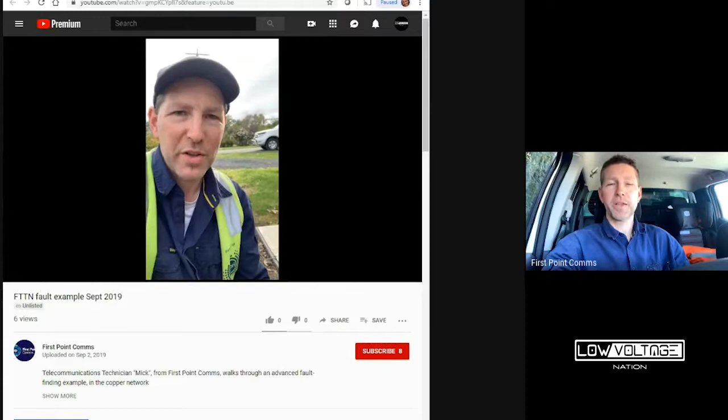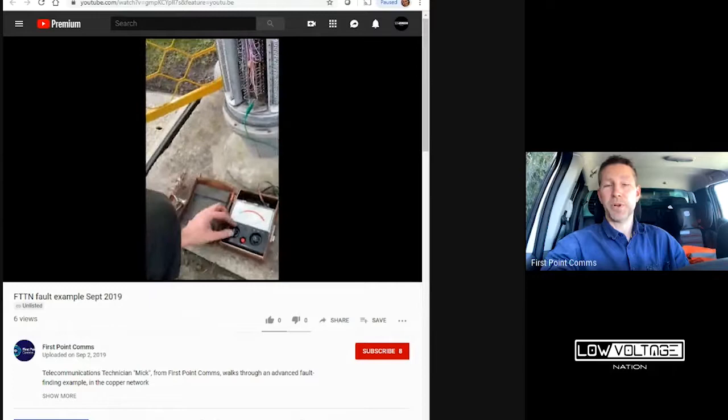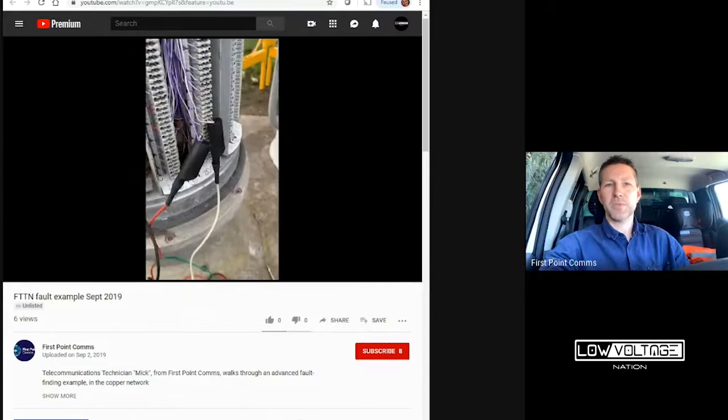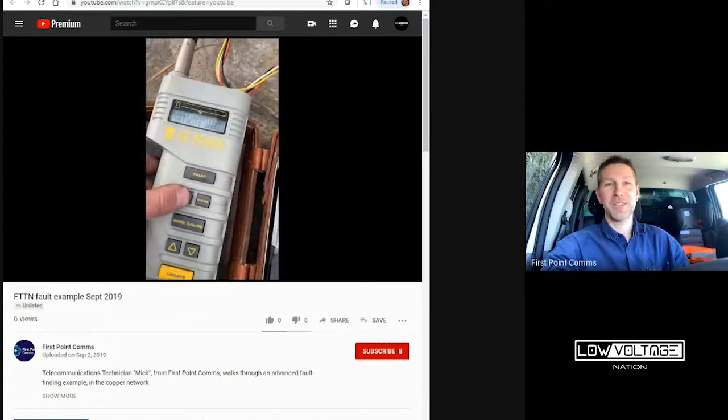So it's, yeah. So to do that, yeah, you need, often tone generators going both ways. Sometimes even get the soldering iron out at the end, depending on the type of connectors at the pillar there. And that, the gray tool there, the one that actually pinpointed where the earth fault was, that's one that I don't, yeah, don't pull that out too often. But yeah, really had them all going. Yeah. That one there, the CZ 3000, we call that one. And that's, I don't know how old that is. I've had that my entire time. I've had that since, you know, the mid two thousands and I'm sure the guy before me had it for a long time before that. So, but it looks super useful just detecting that fault and then telling you where it is, you know, that's some expensive fluke stuff you got to buy, but that thing looks old and it looks reliable for sure. Very reliable.